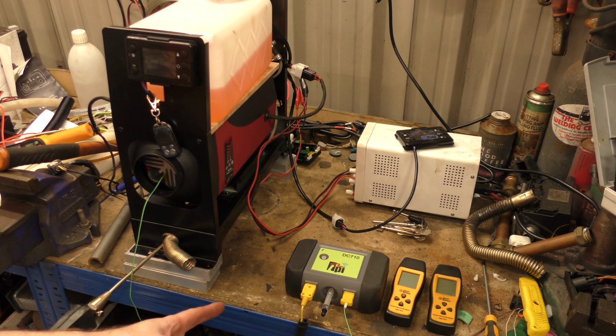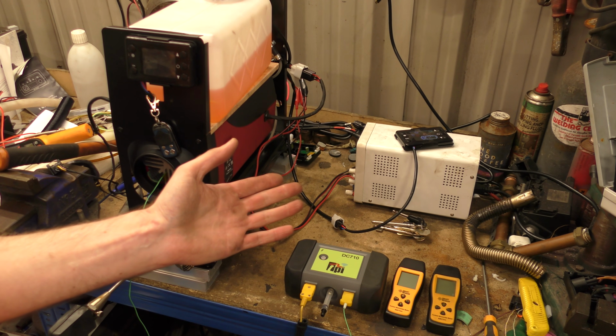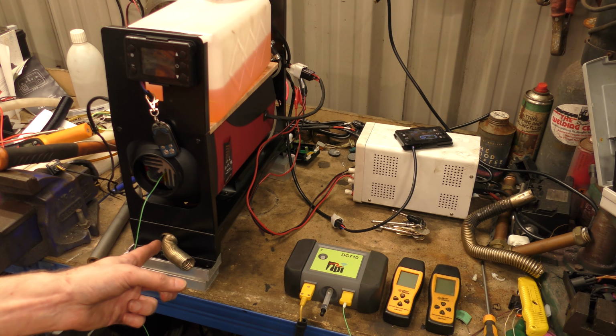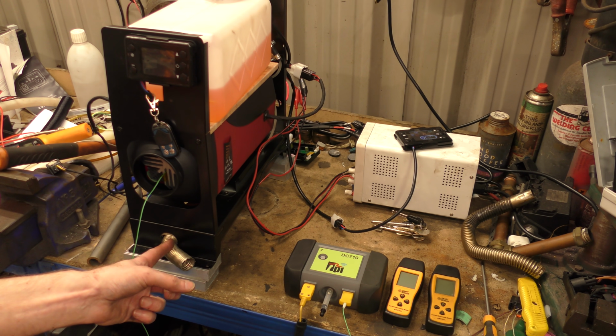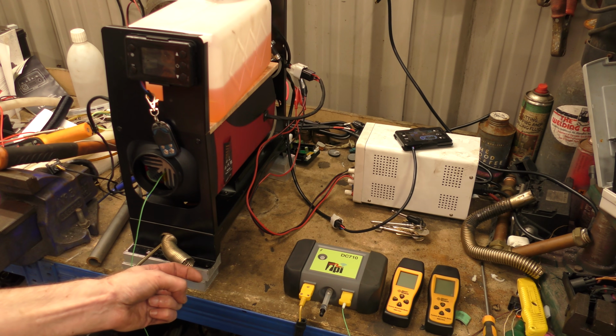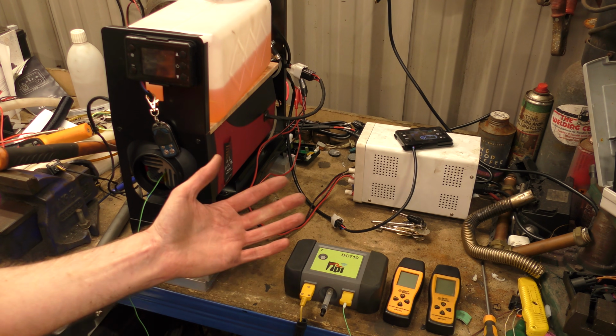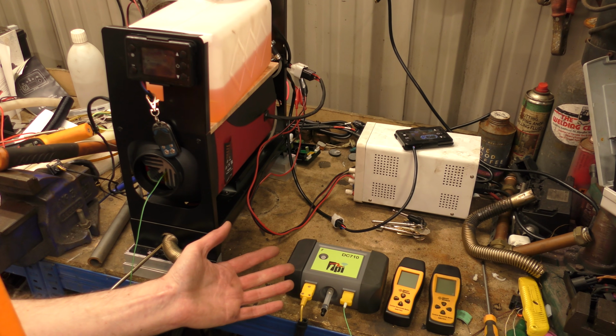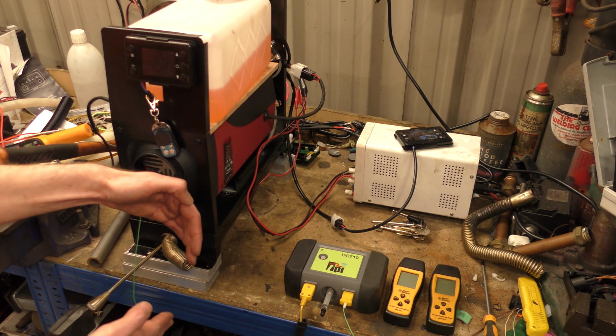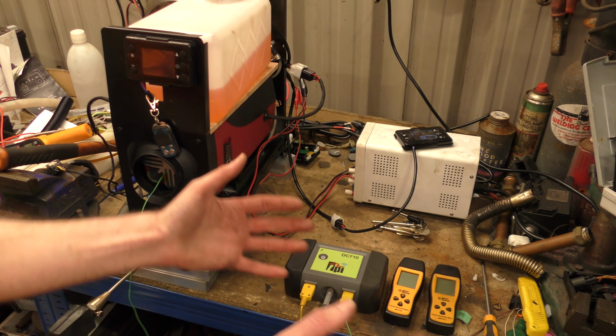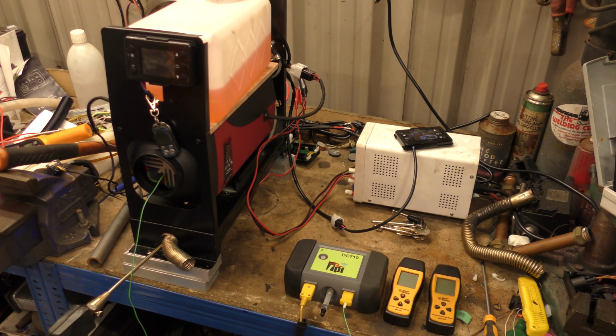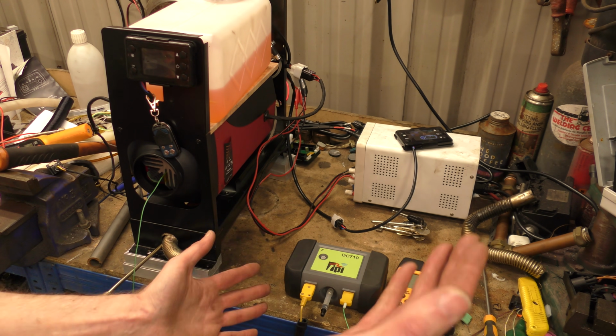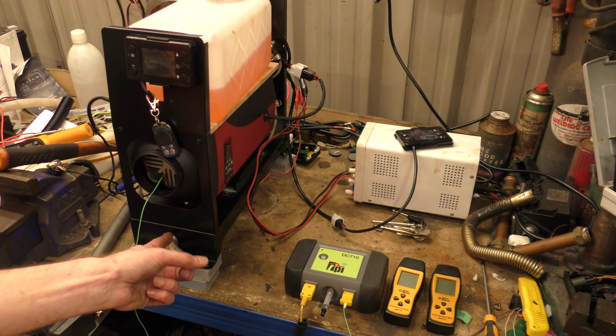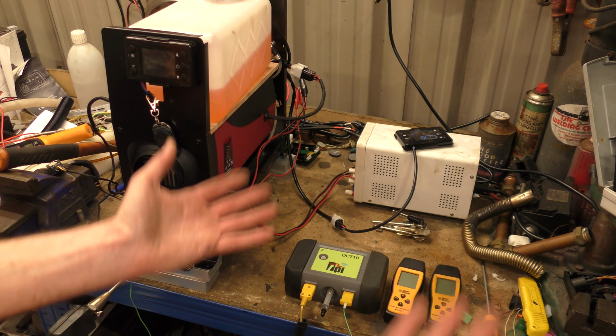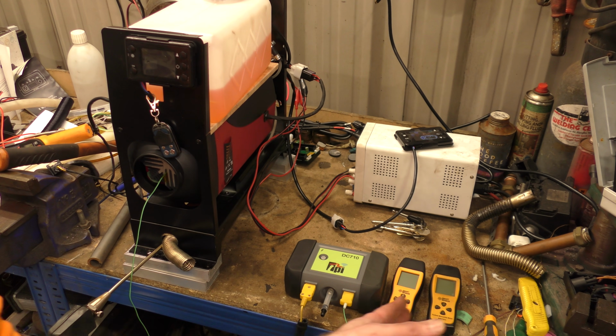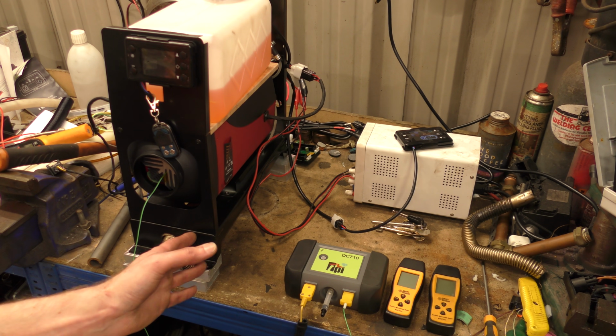Well, I've learned that the carbon monoxide in the exhaust is a lot different than the actual carbon monoxide that's getting blown out. Which, now that I think about it, makes perfect sense, because as that's blown out, it has to pull air alongside with it, and then we're getting a mostly inaccurate reading. But we'll be able to do an offset of what's actually in the exhaust versus what comes out, and we'll be able to see what our sensor should be reading for what's actually in the exhaust.